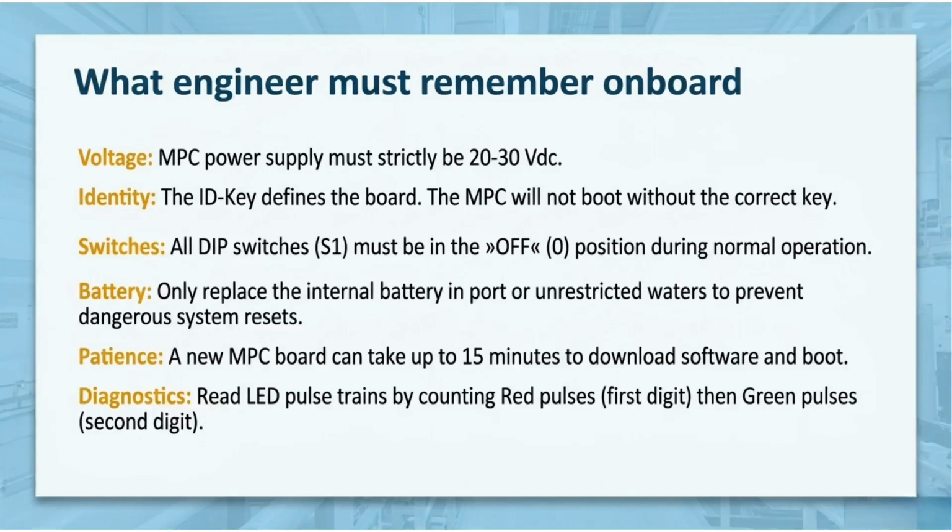Let us lock in what the engineer must remember on board. Voltage must strictly be 20 to 30 volts DC. The ID key defines the board. All S1 DIP switches must be off. Only replace the internal battery in safe waters. Be prepared to wait up to 15 minutes for a new board to boot, and master LED diagnostics by counting red pulses followed by green.